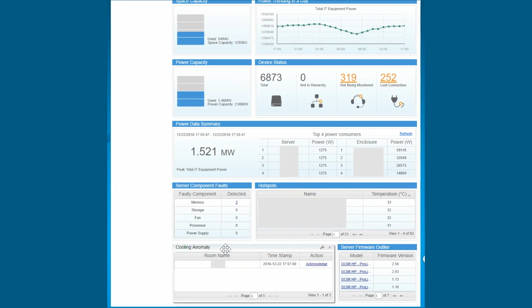But if I see an increase in temperature in 50 devices, even if this increase in temperature is only between 20 degrees to 22, but on 50 devices, and all this happened in 5 minutes, and all of these 50 devices are actually located in a specific area in the data center, maybe a side-by-side rack or maybe a single rack, then of course this is a very, very good indication a thermal issue is developing in our environment.